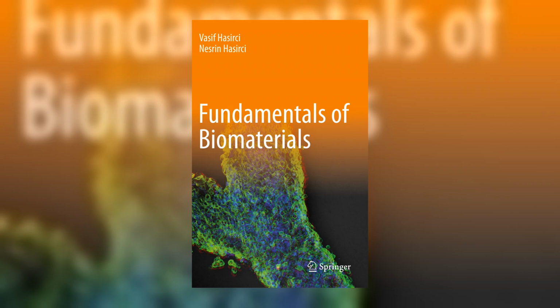Chemical characterization names the constituents and quantifies leachables and extractables. Physicochemical, morphological, and topographical characterization fix structure, crystallinity, and surface, the geometry the body first touches. The surprise is directional. A clean characterization can retire a biological test, since a substance that cannot leave the material cannot deliver a dose. This section explains what characterization means and why it sits where it does in the standard.